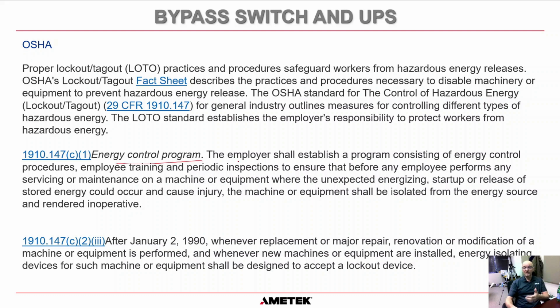Any employer should establish a program that consists of energy control procedures, employee training, and periodic inspections to ensure that before any employee touches anything within either a mechanical or electrical piece of machinery that could be unexpectedly energized, started up, or have release of stored energy, that the machine or equipment shall be isolated from the energy source and rendered inoperative. That is what the OSHA Energy Control Program says.